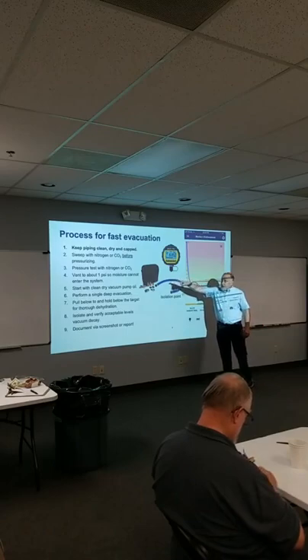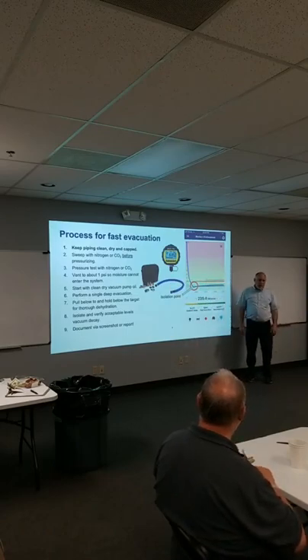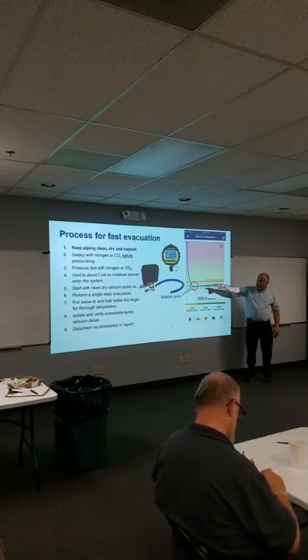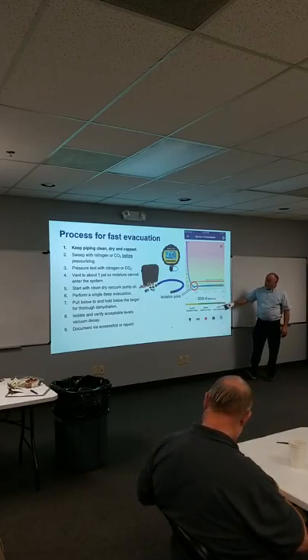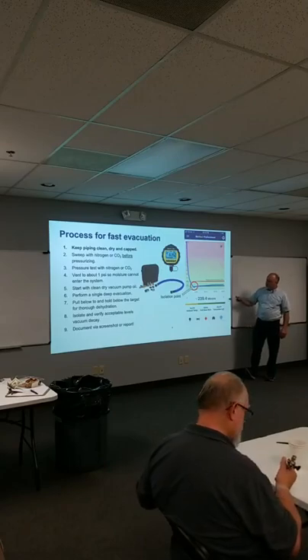After you do your pressure test, you vent it down to about 1 PSI. You do not blow all the atmosphere out of that system. You leave a small amount of pressure on it. And then, obviously, clean vacuum pump oil. We're going to perform a single deep evacuation. This system here, I'm pretty sure it's the same slide. I'll get to it in just a minute.